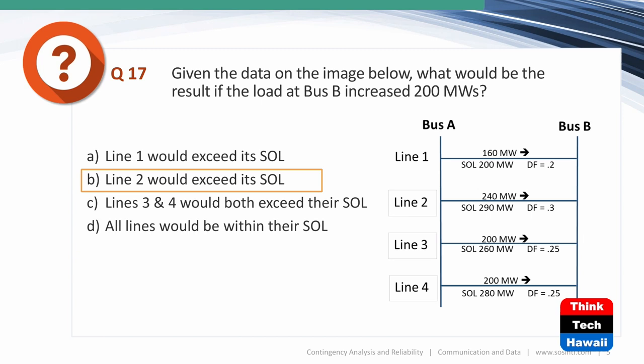For line 1 with a distribution factor of 0.2: 200 × 0.2 = 40 MW, added to 160 = 200 MW — right at the SOL but not exceeding it. Lines 3 and 4 both have a factor of 0.25: 0.25 × 200 = 50 MW added to 260 and 280, giving 310 and 330 — well within limits. Line 2 with factor 0.3 gives 300 MW against a 290 SOL, so answer B is correct: line 2 exceeds the SOL.